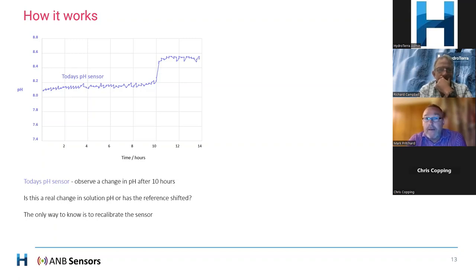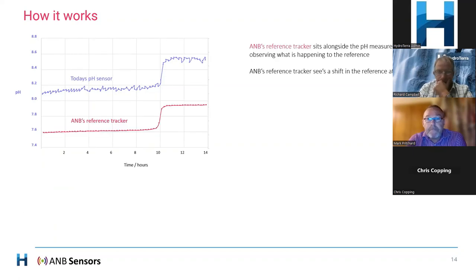So if you look at the next slide: what we do is track the drift. We have a reference tracker electrode within our sensor, and by doing that we track the drift. It's a very simple math equation to subtract the drift from the pH reading, and that gives us the true pH.